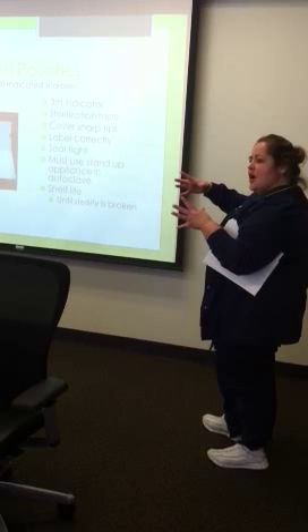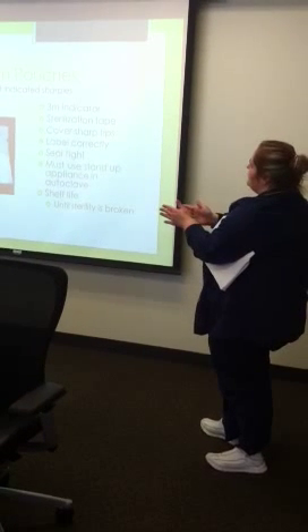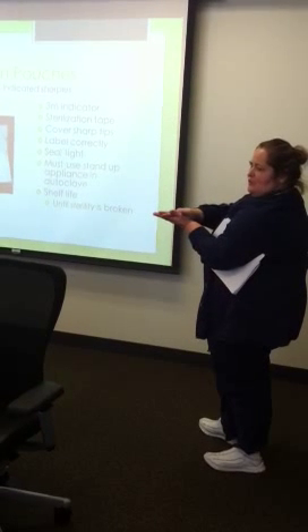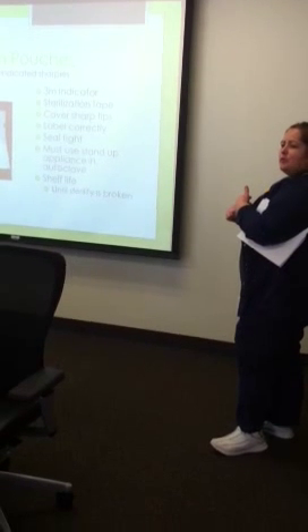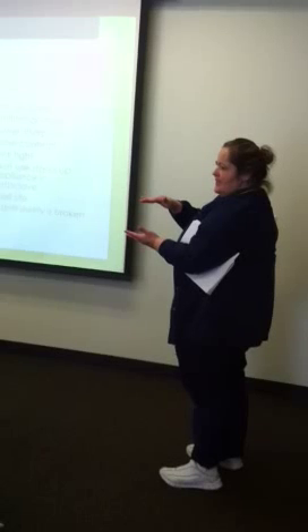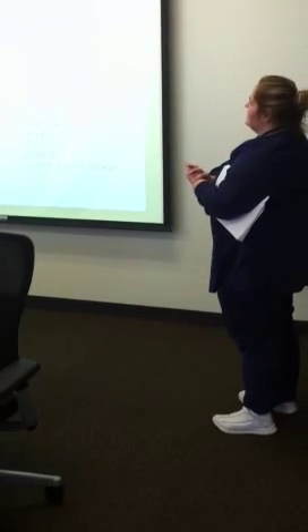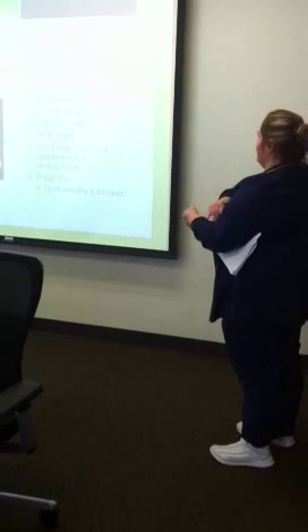There is a stand-up stand that goes inside of the autoclave. I could not find a picture of it, but it's basically a bunch of little slats. So if you've got anything in a pouch, it should not be laying down flat in the autoclave. It should be standing up in there, and that would include like your stent pullers. They should be lined up in there. So our mastectomy sets would go on the trays. The biopsy gun, I've been doing in the stand-up one as well, so they're not touching and they're standing up end to end. And then we talked about the shelf life.